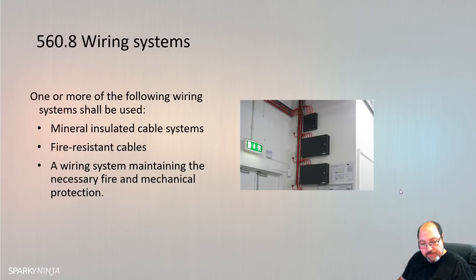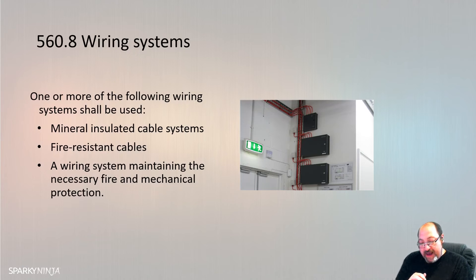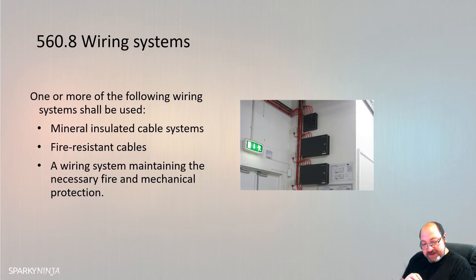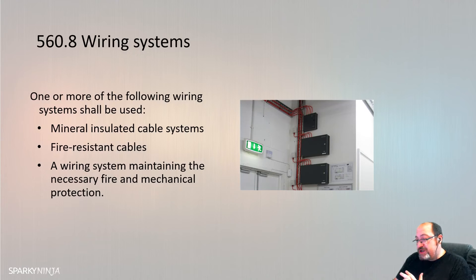For wiring systems, one or more of the following shall be used: MI cable or fire-resistant cables. The wiring system shall be selected to meet the requirements of the relevant code of practice and shall be mounted and installed so that circuit integrity will not be impaired during a fire. Wiring for control and bus systems of safety services shall follow the same requirements as the safety service wiring itself, unless those circuits do not adversely affect the operation of any safety equipment. Supplies can be direct current provided there are two-pole overcurrent protective devices, and switchgear and controlgear for both AC and DC supply sources shall be suitable for both AC and DC operation.